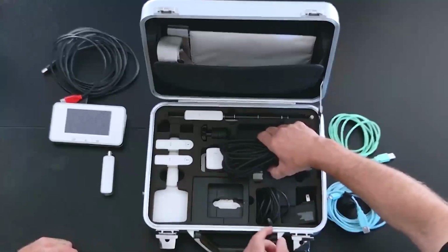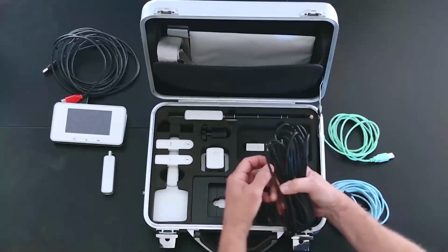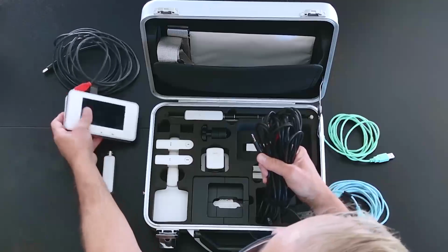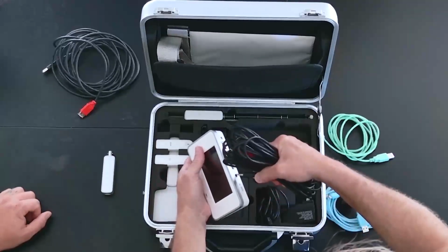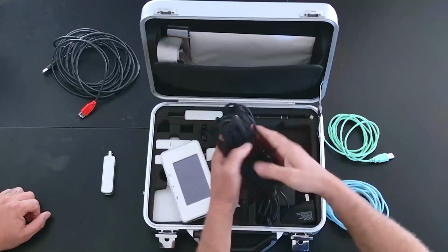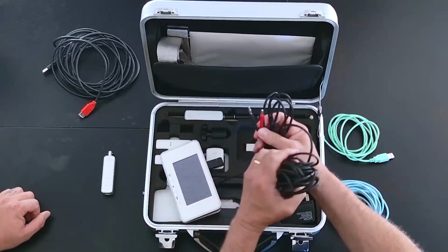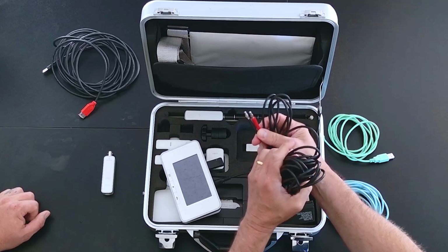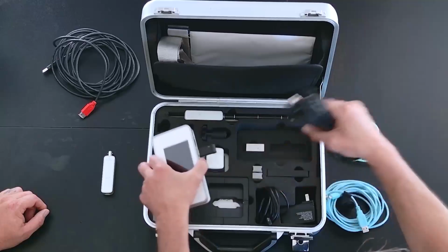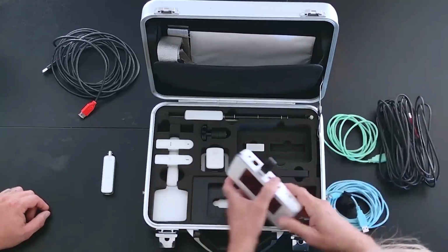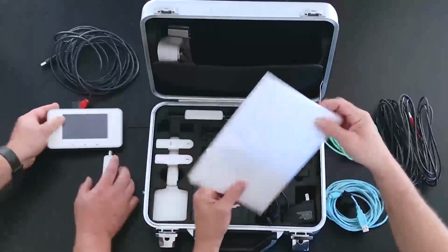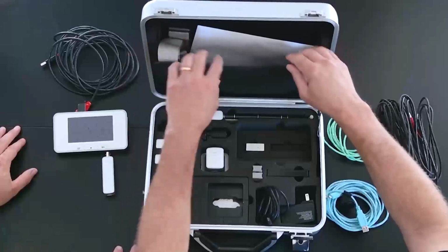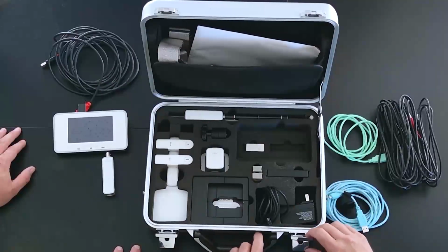Hey, wait. You know something else that's in here? Oh, wait, do that cable. Well, this cable first. This is for the mAs. So Justin mentioned that we have the mAs port on the base unit, and if I connect that and connect the terminals here to the test terminals, the mAs terminals on the generator, you can measure mA and mAs invasively. And then we have the calibration certificates also. Those are cal certs in the pocket, and we have keys. I don't know that anybody's actually used the keys, so I won't even take them.